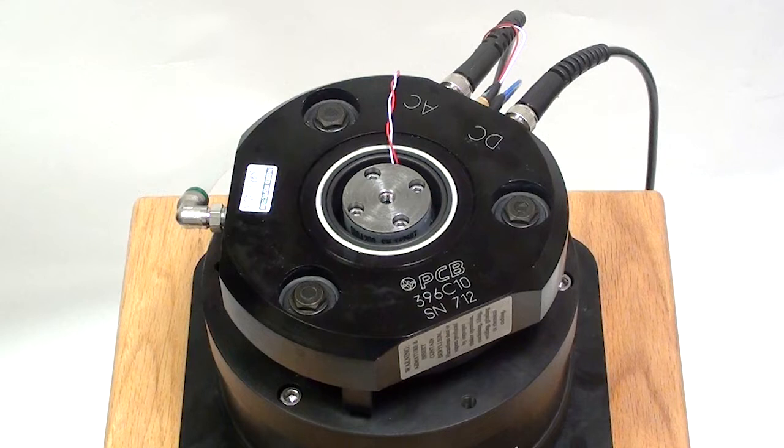In practice, calibration tests are normally performed using the mounting technique with the best high frequency results: stud or screw mounting.